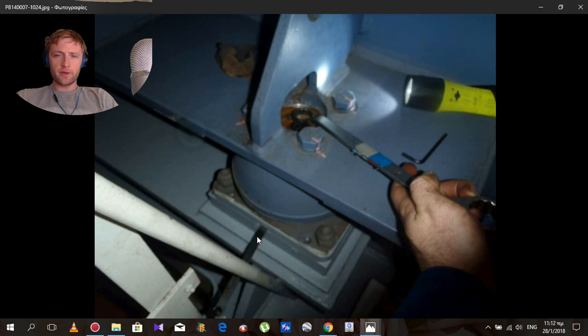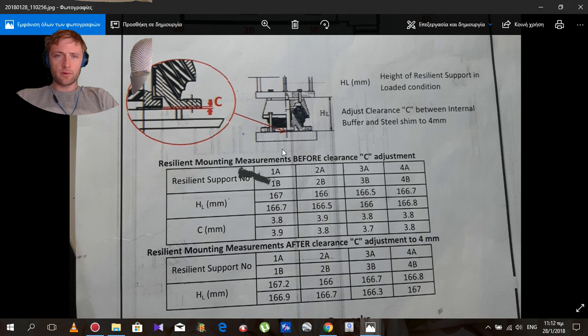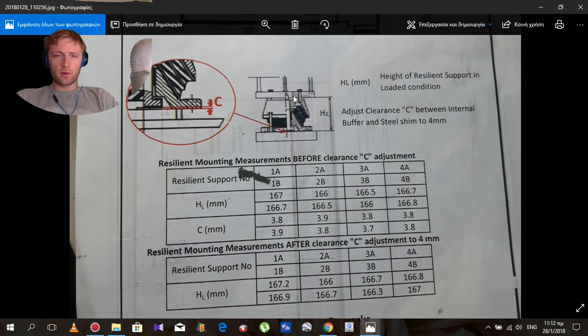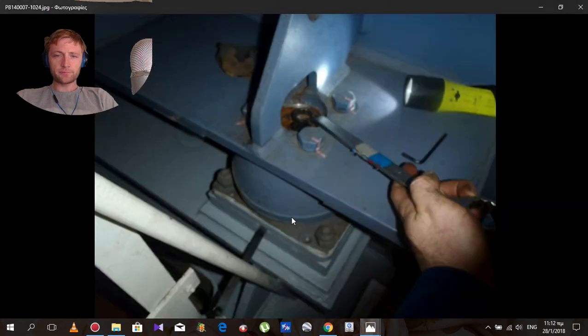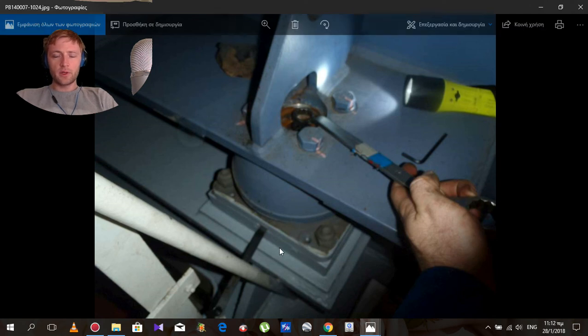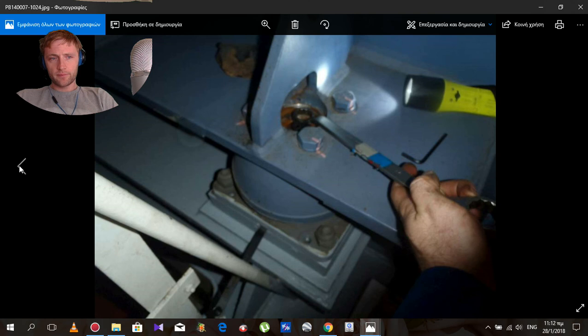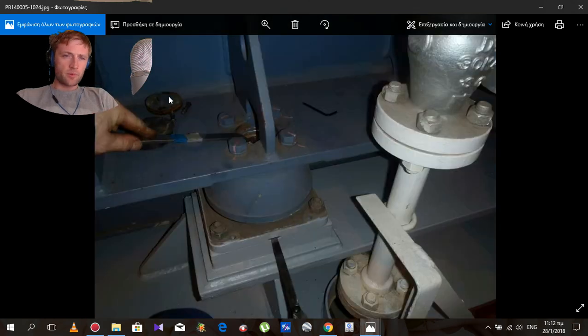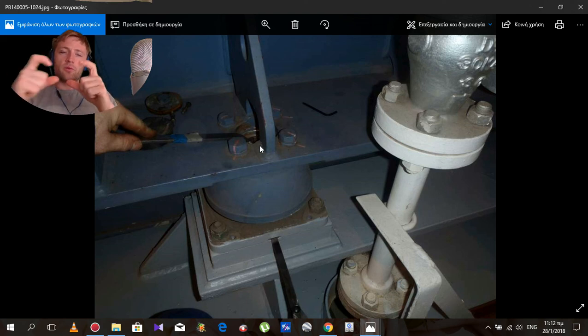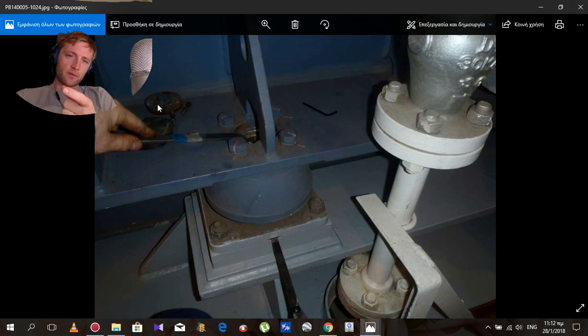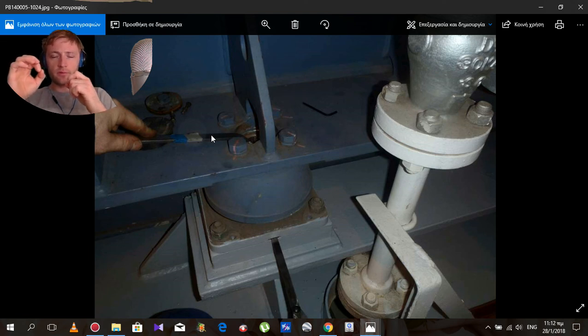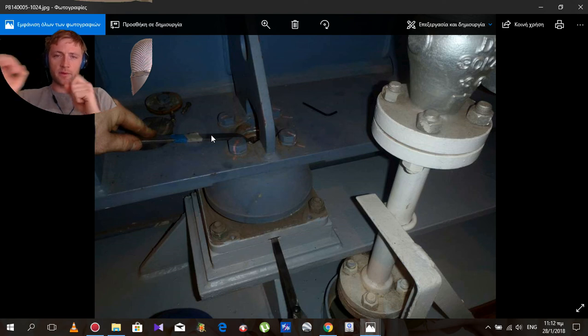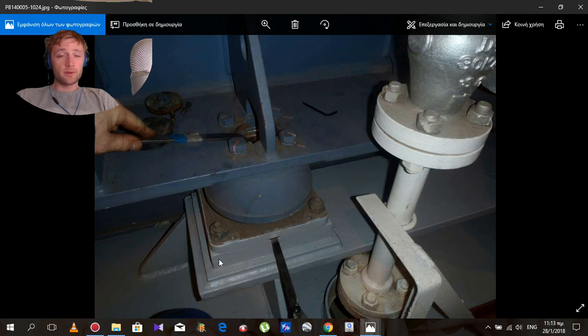I have the feeler gauges here and I'm loosening a cover. There's a cover here you just remove by some screws. When you pull out this cover, you can adjust by this nut here. You turn a little back and forward to see where your clearance is. This is the cap, the locking allens which lock here. When you adjust to, let's say, 4mm clearance and put back this cover, you need to find the holes. Sometimes if it's moved from these holes, you cannot enter that one. You must find exactly the golden point.